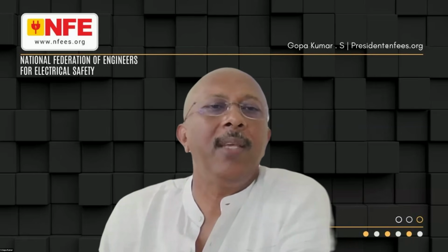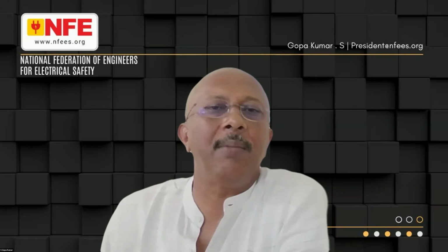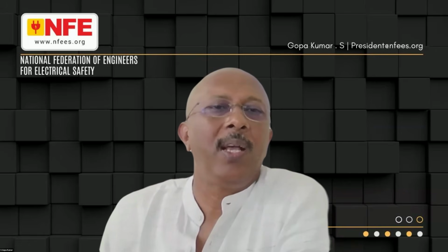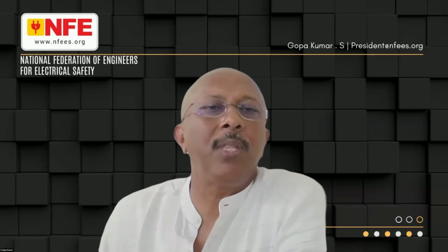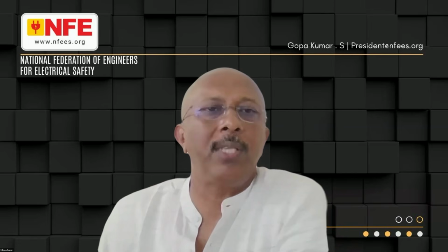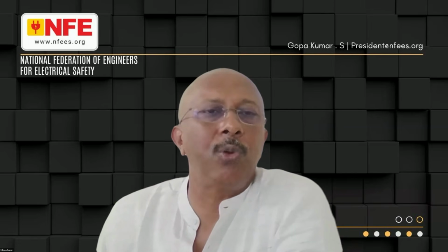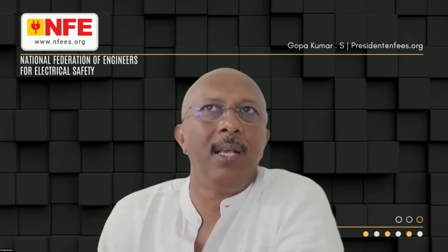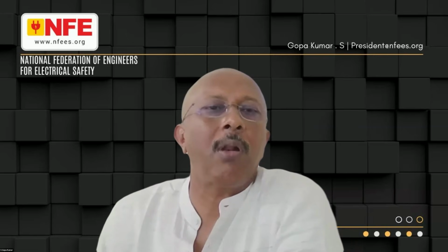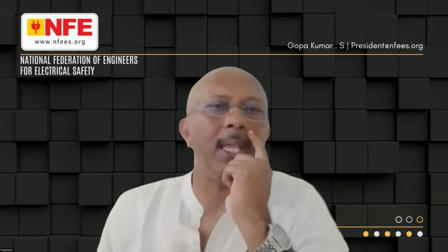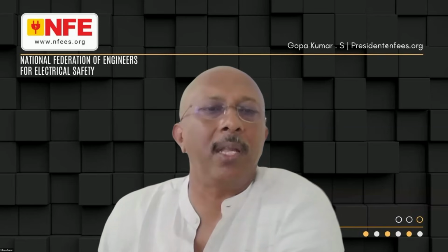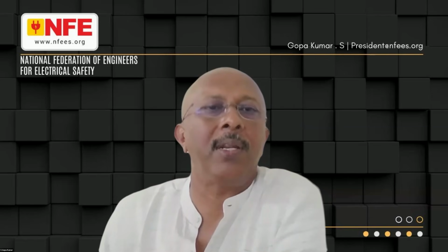Mr. Rajan Kare asks again: does the LA system need a separate earth pit? Absolutely not. It must be bonded to the electrical system. Mr. Prabhakaran is asking which earth electrode is best, copper or aluminum? Mr. Prabhakaran, please note that aluminum cannot be used as earth electrode. Aluminum must be used only in exposed places, through the surface of a wall, not inside the soil or inside the concrete. Aluminum cannot be used in such applications.